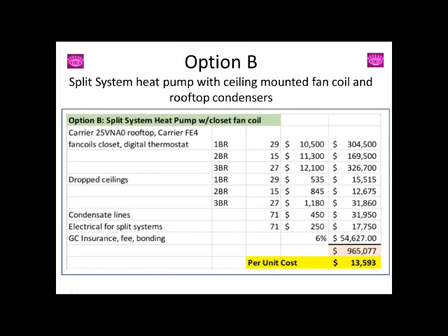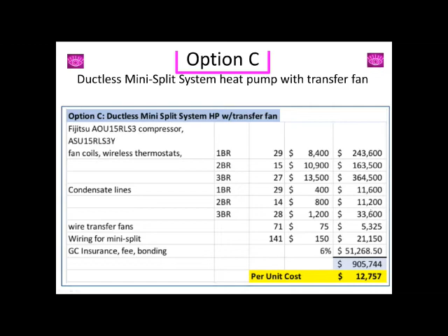Option C, this ductless mini split, is what we selected as the final specification. It has a single wall-mounted fan coil with transfer fans, as opposed to option B, which has multiple fan coils, one in each room. It was $60,000 less than the heat pump with traditional ducting.